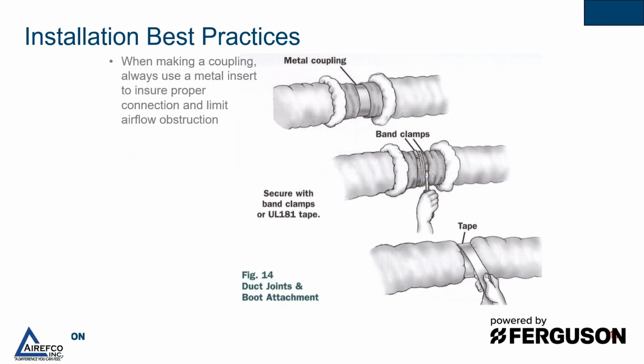On a long run of flex duct where you have to connect 2 different pieces, make sure that when you're making a coupling that you always use a metal insert to ensure proper connection and limit airflow obstructions. You also want to secure it with clamps and seal it with tape.